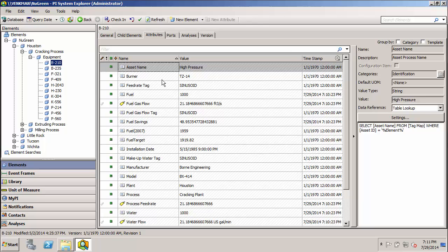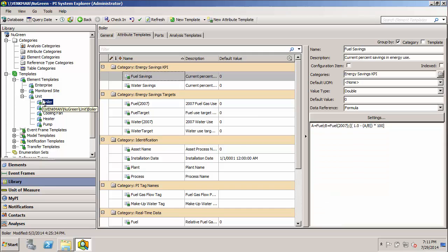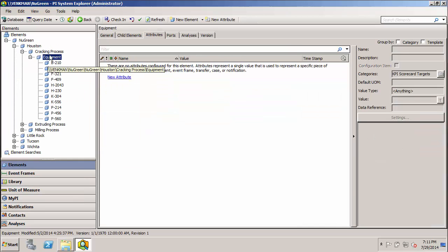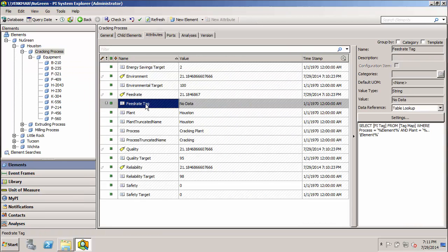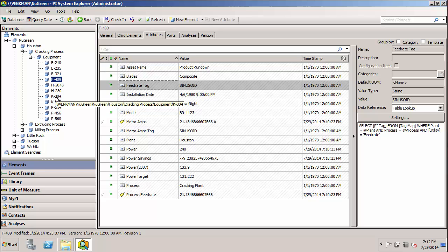So a good approach is usually a middle ground where we spend some time sketching out this hierarchy, getting an idea of how we might want to do some template inheritance so that we have a set of attributes across as many pieces of equipment as possible, and thinking about some of these calculations and any data that we would need from lower levels to feed into those, what types of things we need at the equipment level, but also going ahead and including other available pieces of data for our equipment and not ignoring those that aren't needed for the calculations, because those can often be found to be useful later for some other monitoring purpose or some kind of new initiative, such as an efficiency initiative or an environmental initiative.